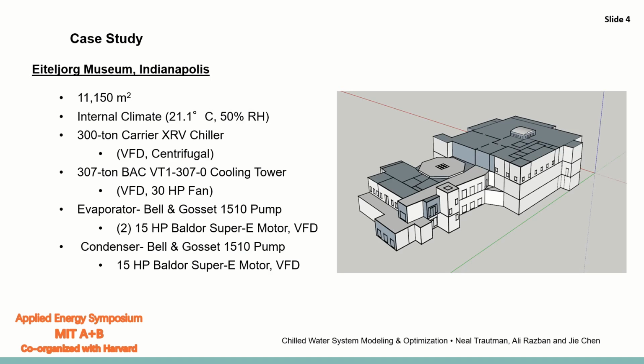We performed our case study at the Eiteljorg Museum in downtown Indianapolis. It's a large facility with a strict internal climate in order to maintain the stability of the exhibits housed within the museum. The chilled water system is comprised of a 300-ton Carrier chiller, a 307-ton Baltimore Air Coil Company cooling tower, two 15-horsepower evaporator pumps, and a single 15-horsepower condenser water pump. Each of these pieces of equipment is actually already fitted with a VFD. However, for the evaporator and the condenser water pump, the building automation system has no internal control logic to control these VFDs, so they operate at 100% year-round, regardless of any external or internal variables.